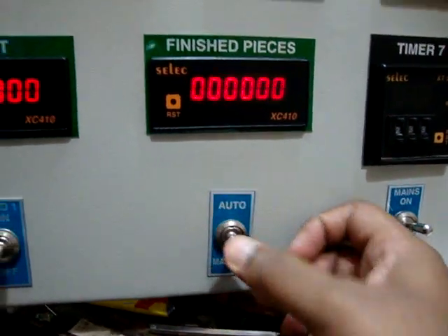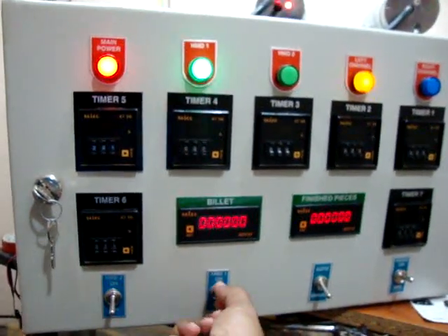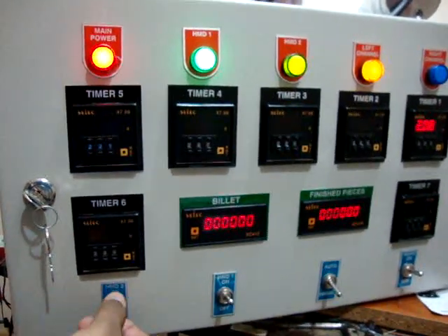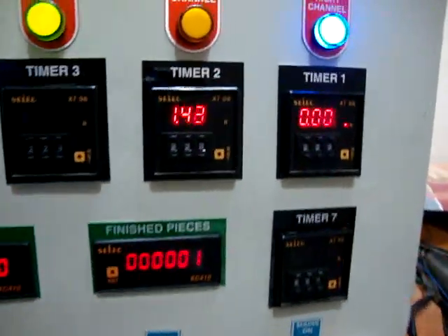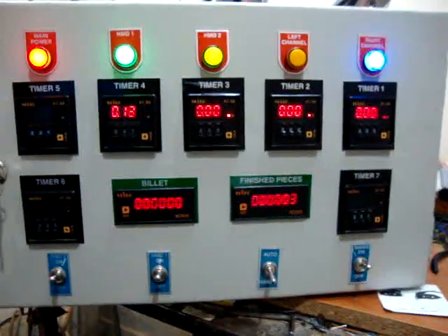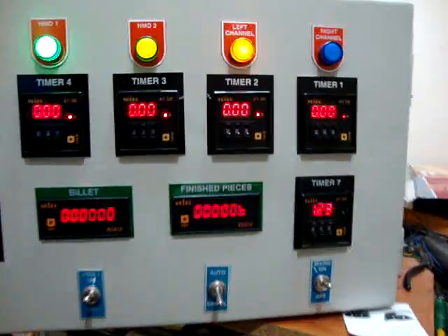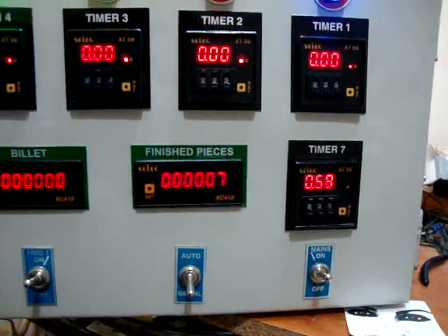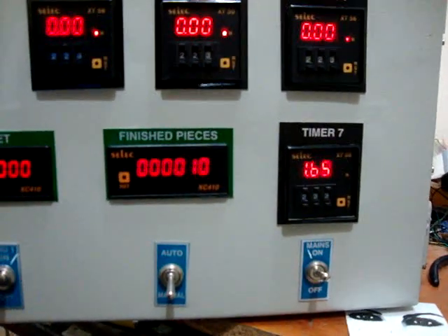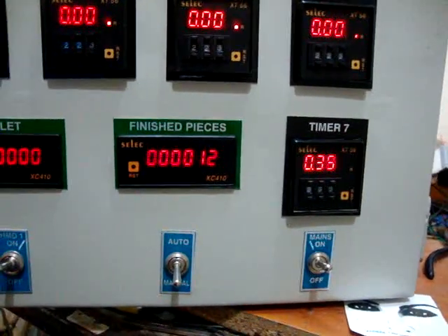It's already in manual mode. Now we are going to turn on manually and see HMD 1 lamp. When both the lamps are on it's an AND condition and the process begins. There is a logic behind this — to bypass the last piece we need to take AND condition. In case there is continuous metal coming, the last timer will loop back and reset.